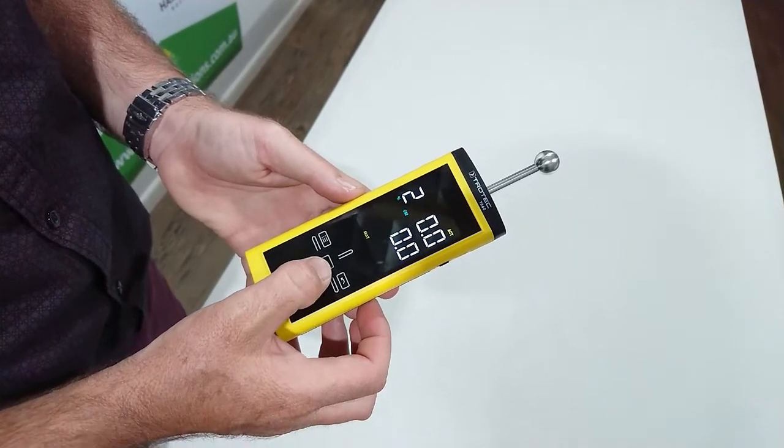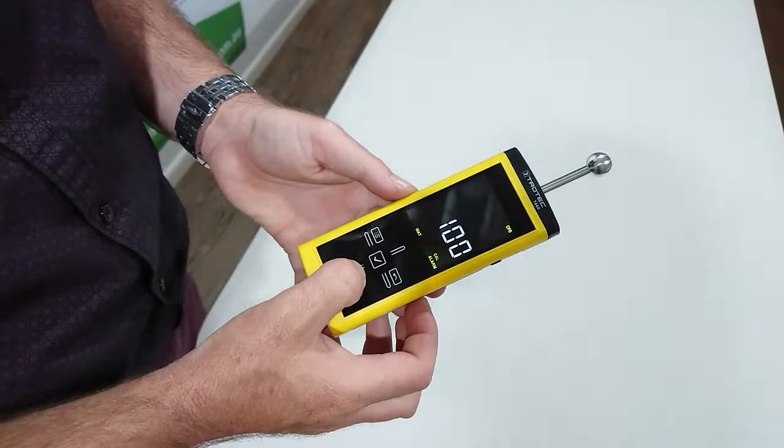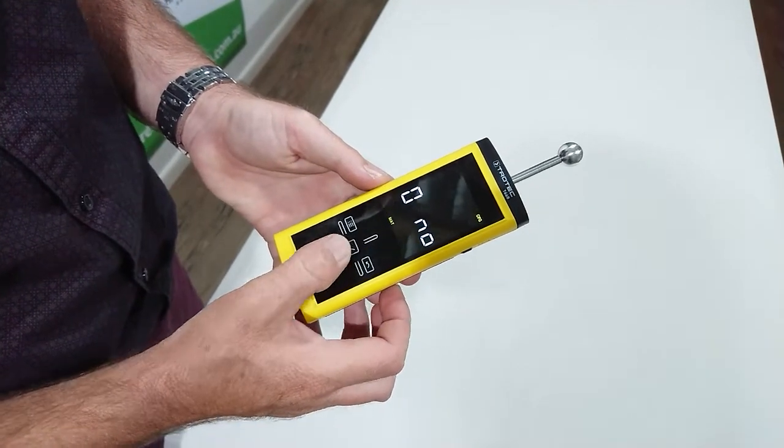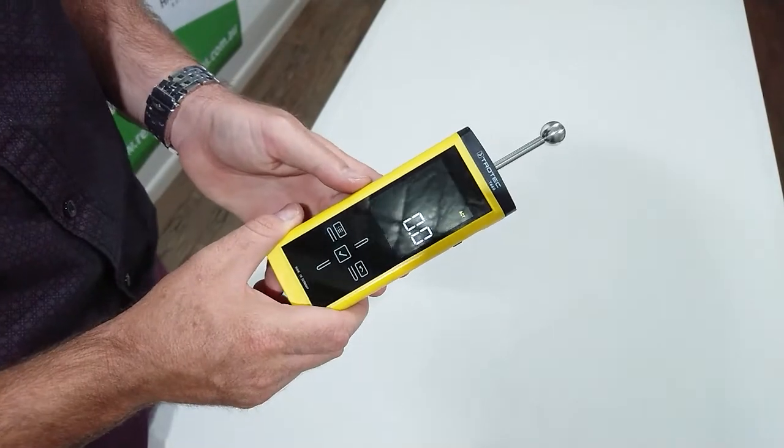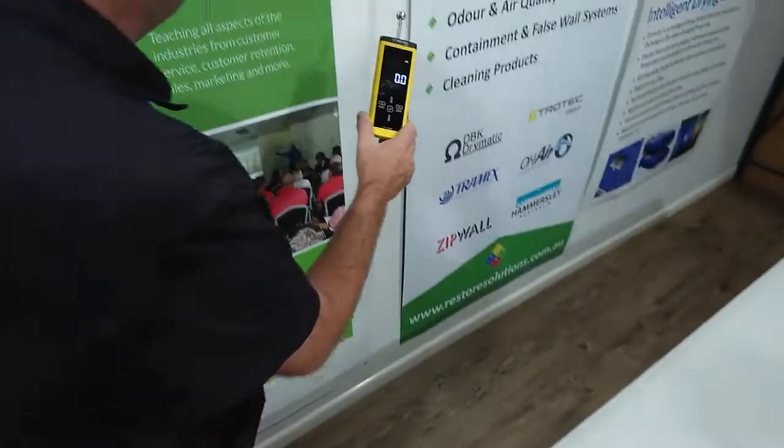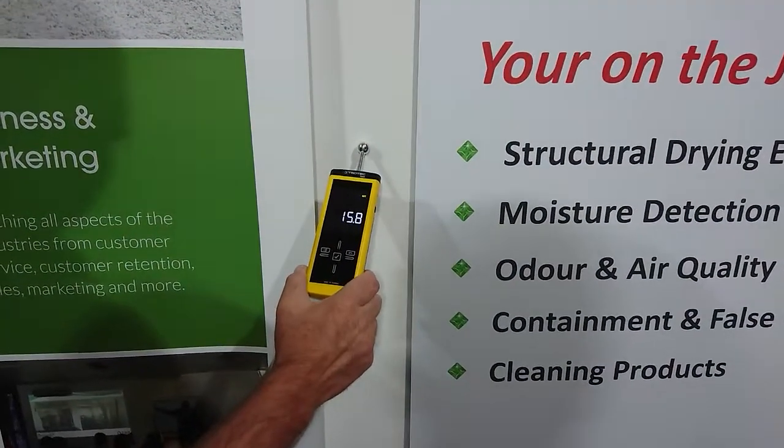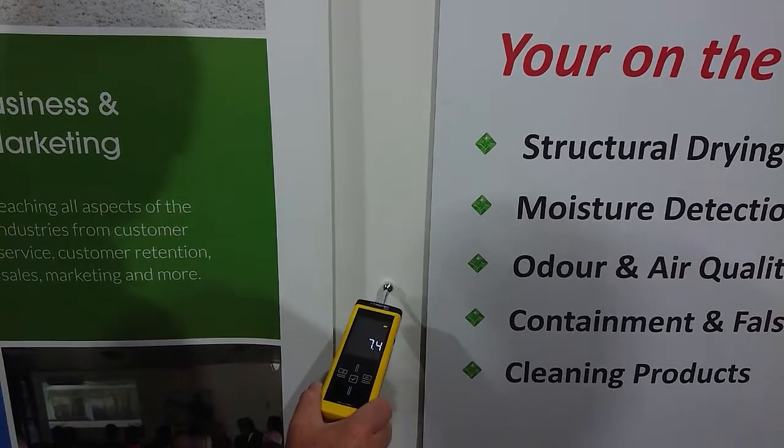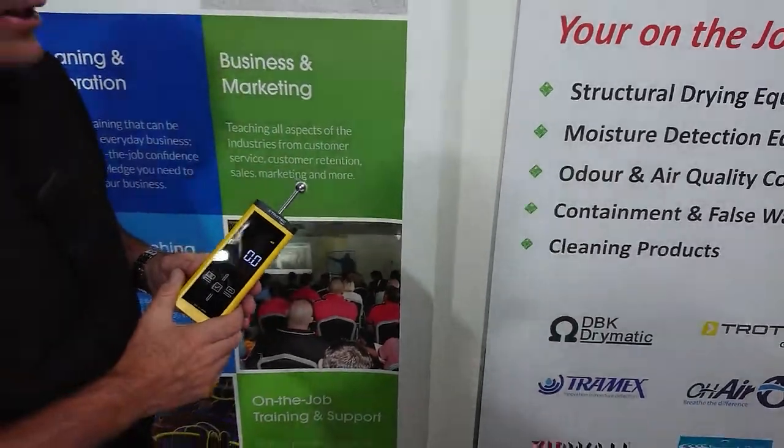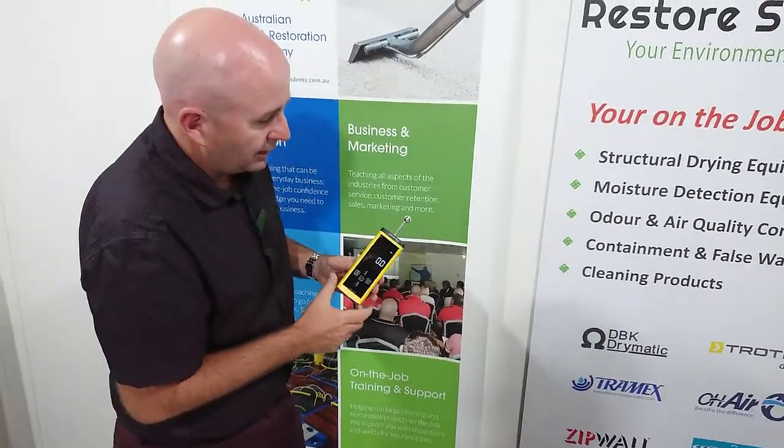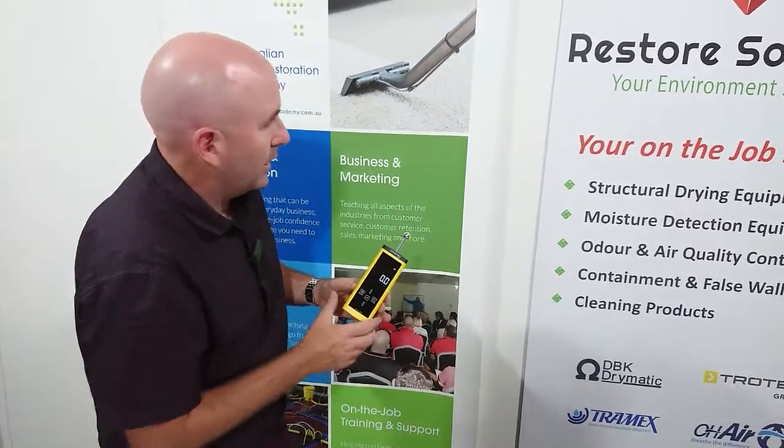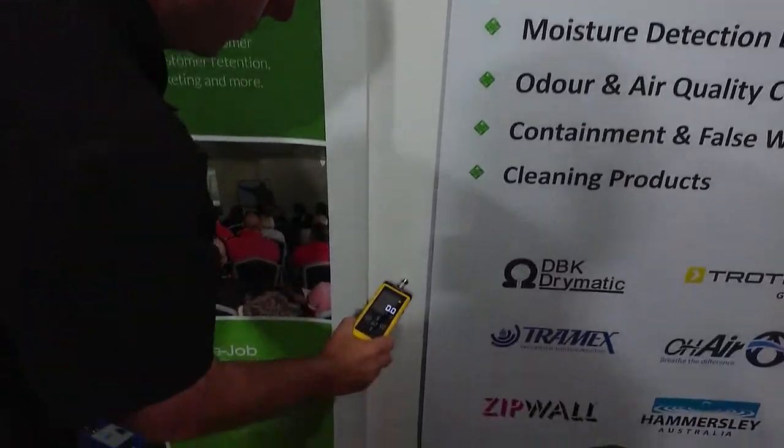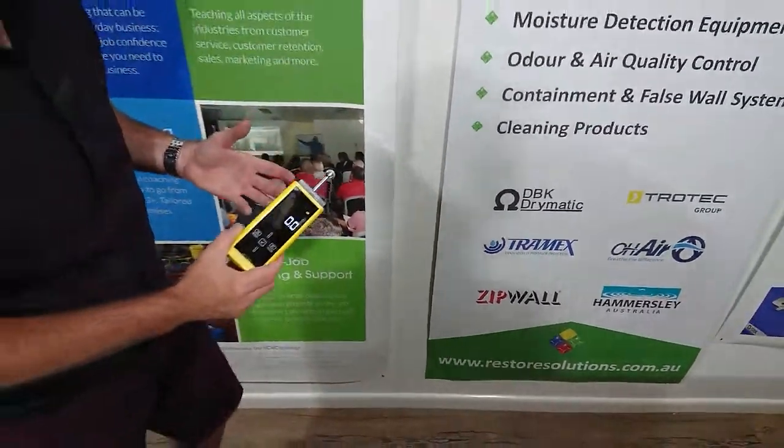So what we're going to do is go back from there and we'll go into the building materials. With the building materials it's a relative scale. So I'm just going to show you on this wall over here. We've got a reading and people say what does that reading mean? So it's all relative, it's a relative scale reading. What you've got to do is go find a dry area with that meter. So in our dry area we're reading eight, nine, eight, so we're getting a rough average between eight and nine.